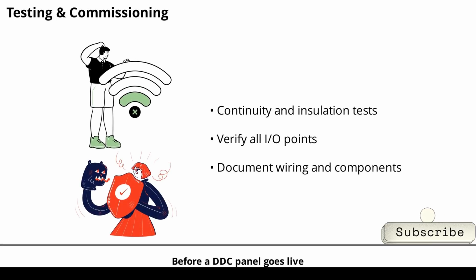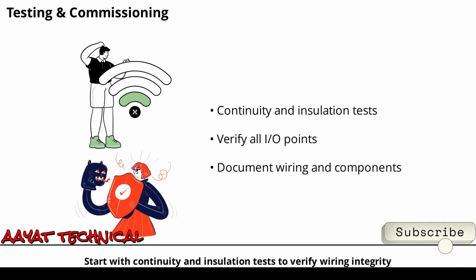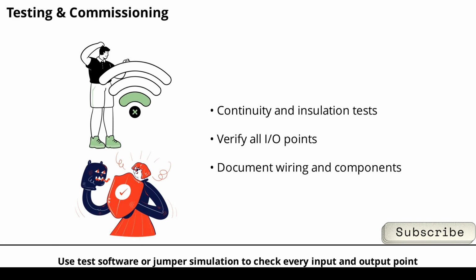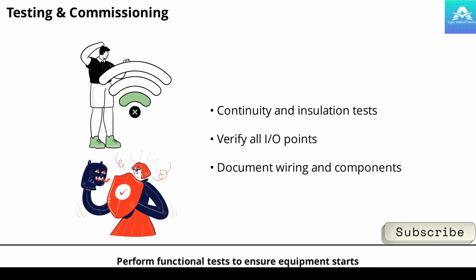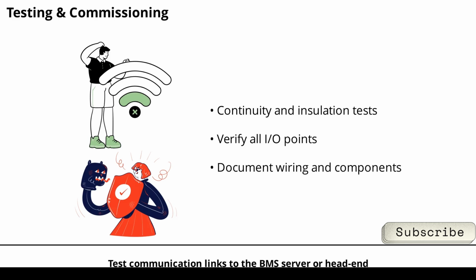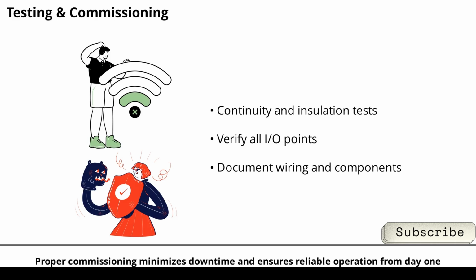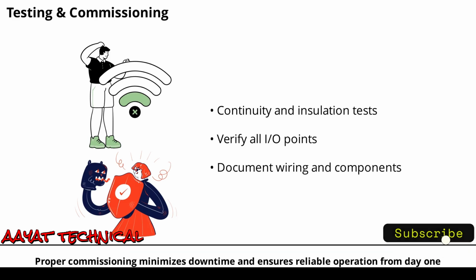Before a DDC panel goes live, thorough testing and commissioning are essential. Start with continuity and insulation tests to verify wiring integrity. Use test software or jumper simulation to check every input and output point. Perform functional tests to ensure equipment starts, stops, and modulates as intended. Test communication links to the BMS server or head end. Finally, label and document all wiring and components for future reference. Proper commissioning minimizes downtime and ensures reliable operation from day one.